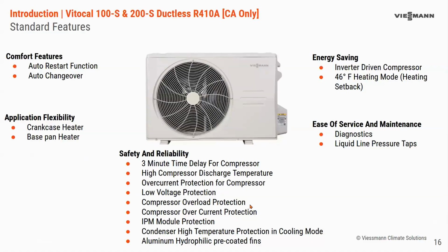So that was the overview of the single zone outdoor units, the multi-zone outdoor units, the ranges, capacities, the performance generally, but some standard features that all of the outdoor units also have, just a little bit more detail. There's a long list here, as you can see, but starting with the comfort features. So there's an auto restart and auto changeover. The auto restart, if there's an interruption in the system, a power surge or a temporary on-off situation, after the time delay for the compressor is over, the system will resume to its previous set point. So it has a memory storage of that. Also, at the indoor unit, you can select auto for auto heat cool switchover.